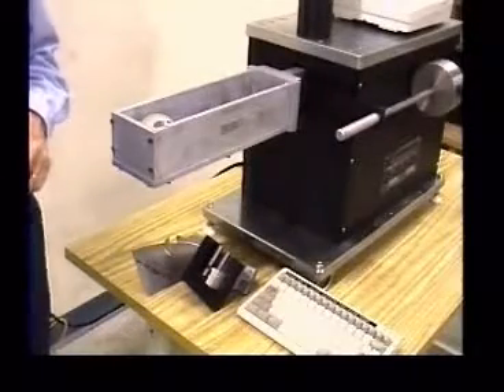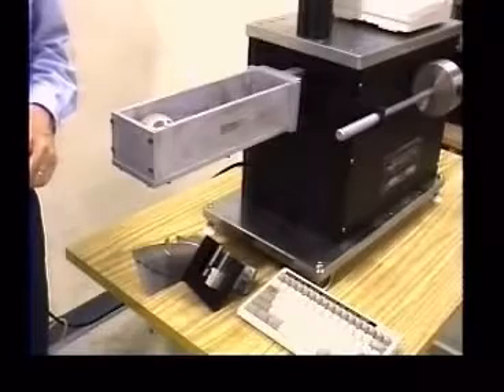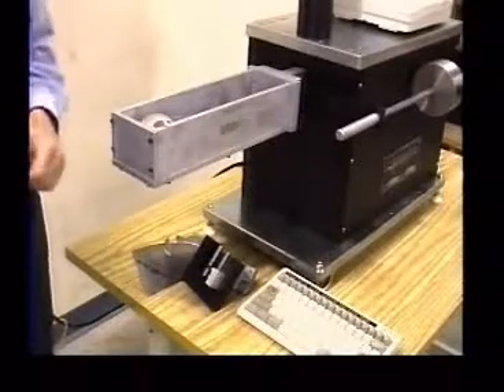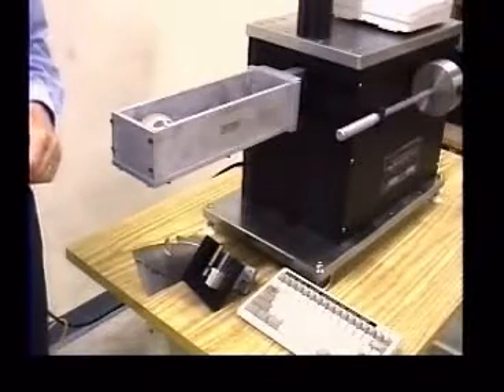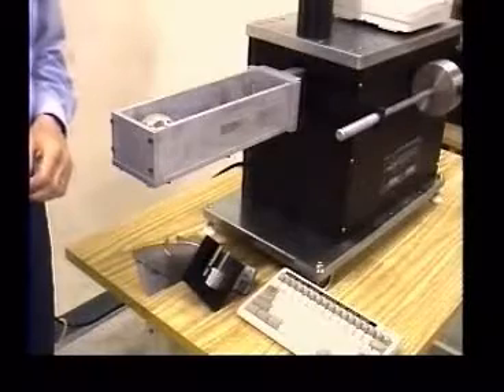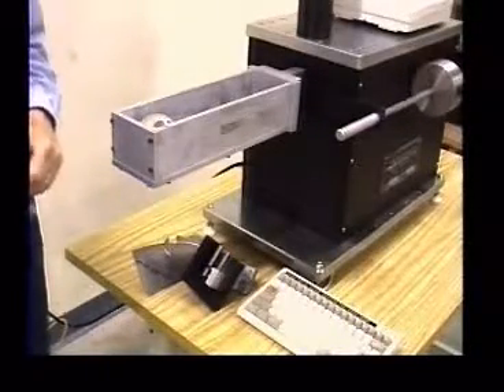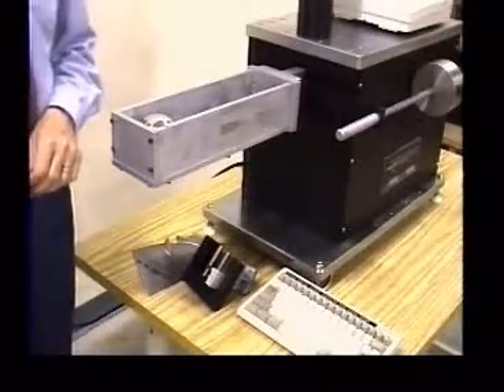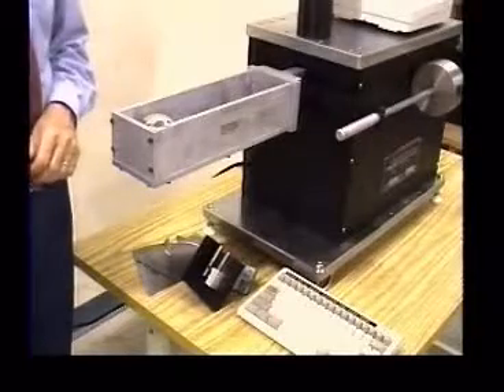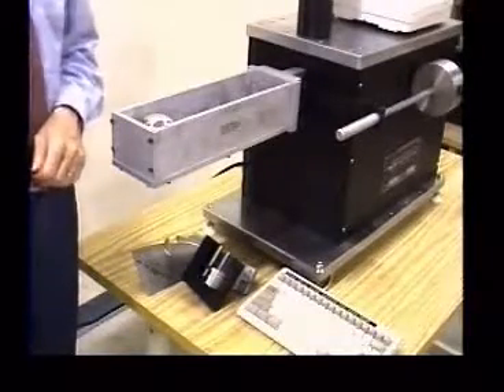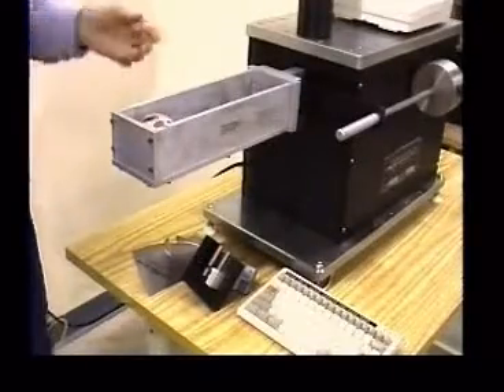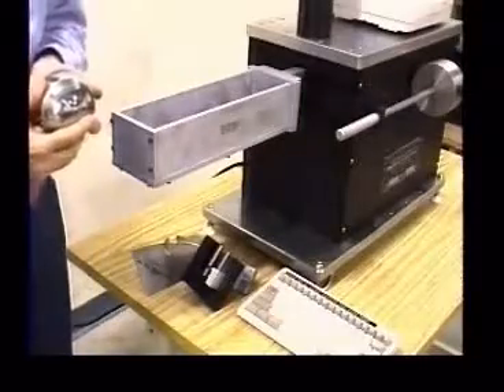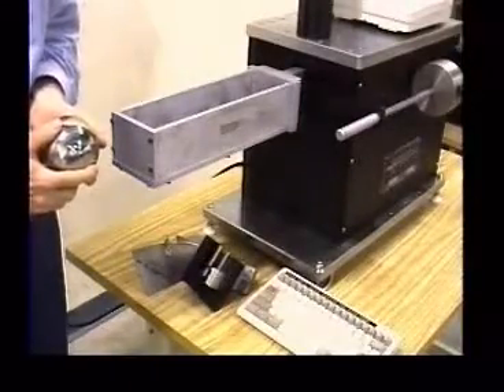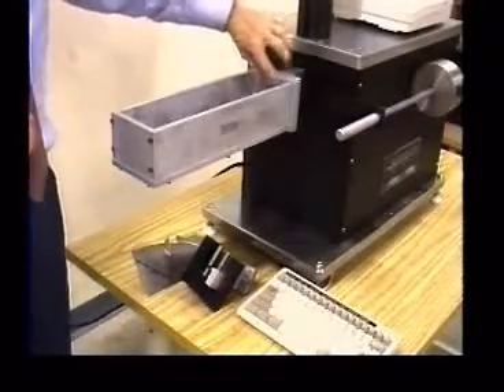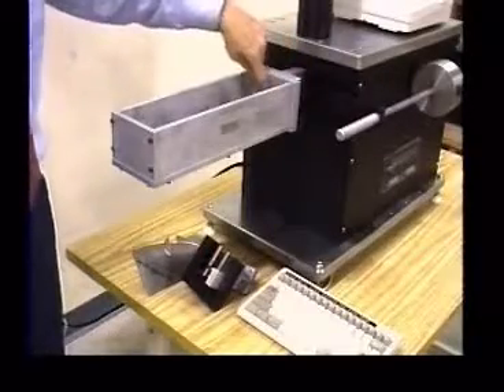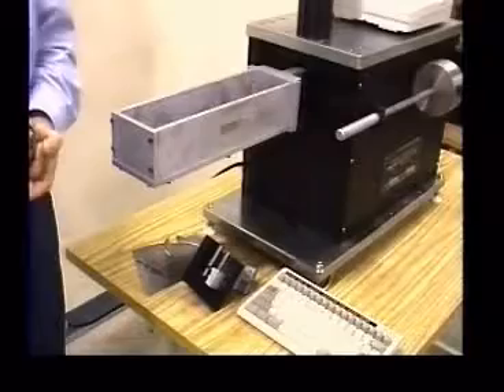Because of the extremely high accuracy of this machine, we had to develop a new method to calibrate the machine. Traditionally, moment weight machines are calibrated using rods and cylindrical weights or using a knife edge and a hanging platform. But neither of these methods would be acceptable for a machine that has an accuracy that approaches 2 parts per million. So what we developed is extremely simple, but also very elegant. The calibration system consists of a perfectly round ball that has been machined to a very high tolerance, and a cavity that has 2 surfaces whose distance has been determined with an extremely high degree of accuracy.